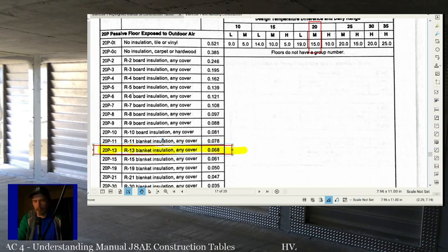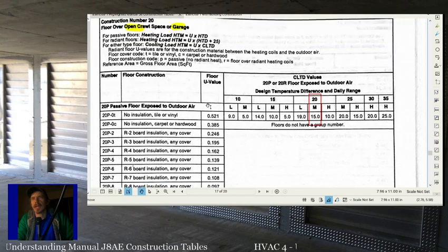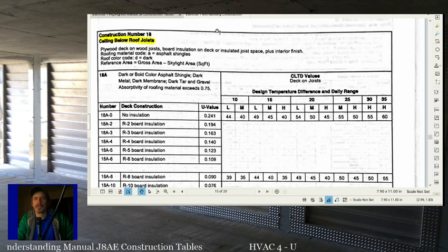And we're also dealing with the heat stored in the ground outside, the daily range, you know what I mean? A city with a lot of blacktop, a lot of asphalt in it, is going to stay warmer longer than out in a rural area where there's less things to hold the heat. Less construction. So those are both a little different situations. There's a lot of other factors in cooling is what I'm getting at, right? So since there's a lot of other factors in cooling, you can't just say, oh, the temperature difference times our U value will equal the BTUs gained.